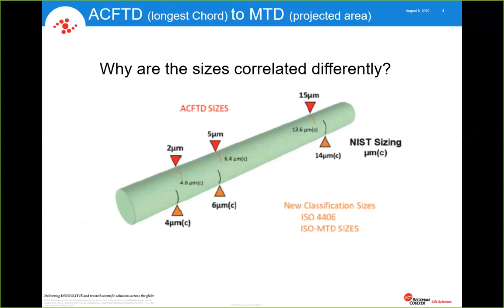But anyway, we didn't have the sensitivity with the 400, so that's why we created the 100. It has the same flow cell. It's a 400 by 1,000 micron flow cell as far as the aperture size, but the electronics were optimized to accommodate the ISO medium test dust calibrations and that minimum sensitivity. And so that is why we have to specify the HRLD100 sensor going forward.